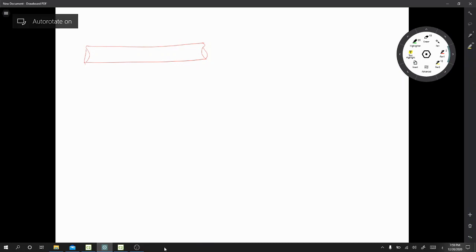What is the meaning of the pressure thrust? Pressure thrust, actually, if we draw the pipe like this, the pressure thrust is the pressure inside the pipe. But why don't we consider it in the normal cases? Because of how we calculate the force. The force is equal to K times X. X is the change in length or the elongation, and K is the stiffness.